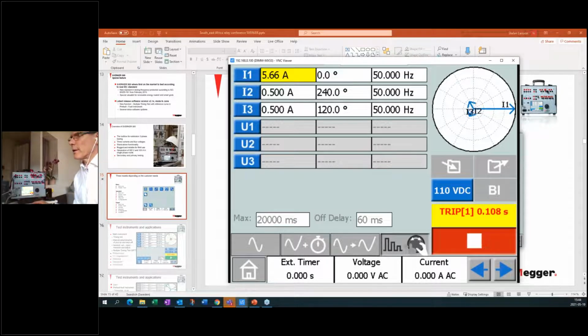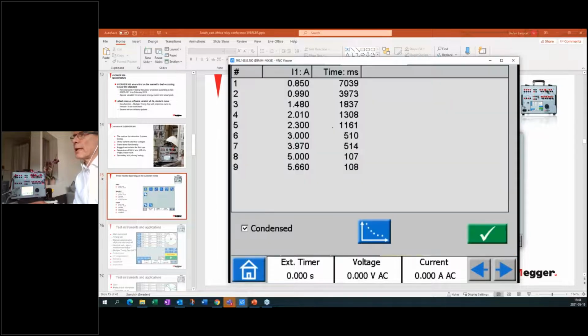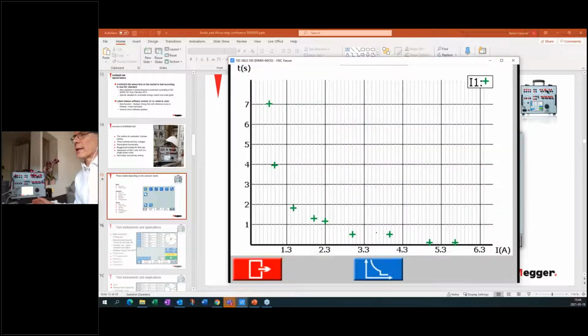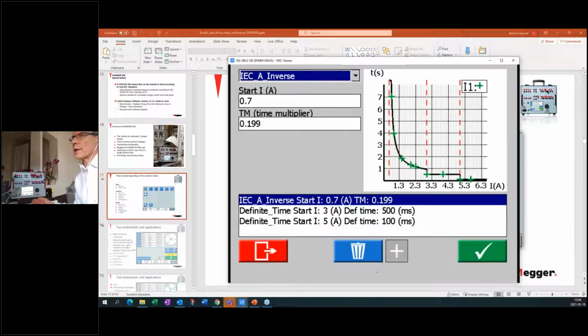Okay, when I'm taking my points, I push the stop button. I can see the currents and the timing for all the current levels, different levels. I can see the graph with the test points I have made. Also, if I would like, I can have a reference graph to set according to the settings in the protection.